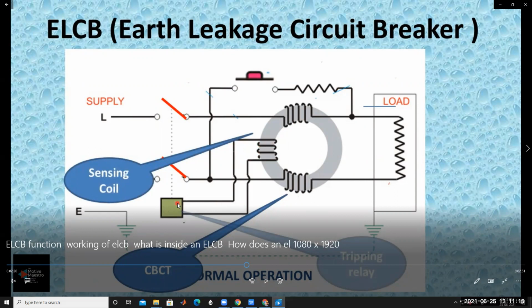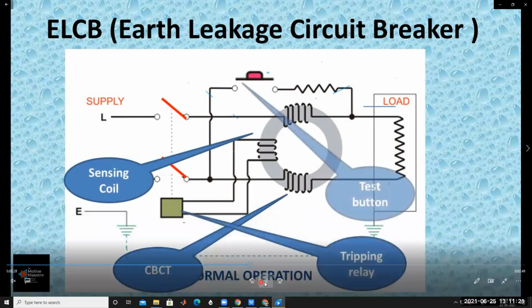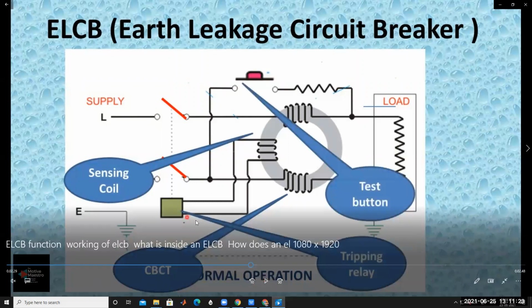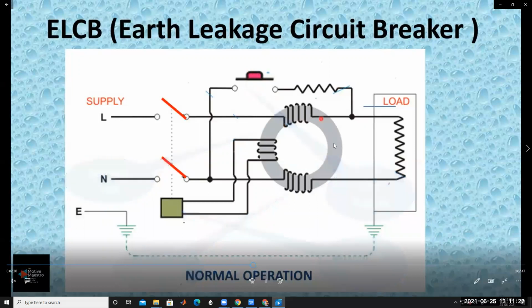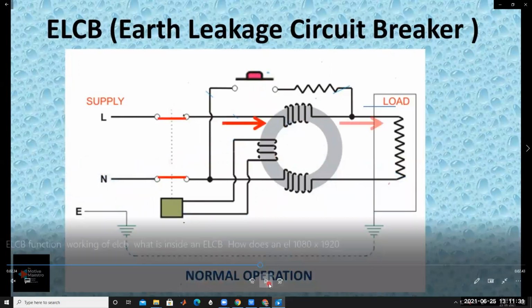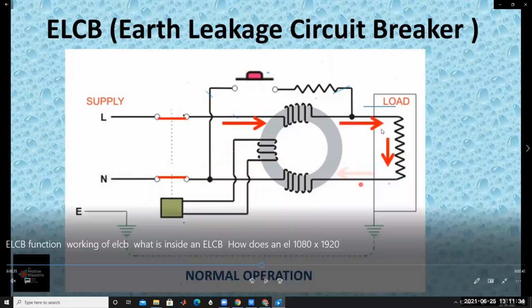It's connected to the trip circuit. This is called the CBCT, and this is called the tripping relay, and this is called the test button. To test whether the circuit breaker is working properly or not, it can be tested by using the test button. So under normal operating conditions, this is called the load. The load may be a fan, fridge, TV. Under normal conditions, this is the current direction.